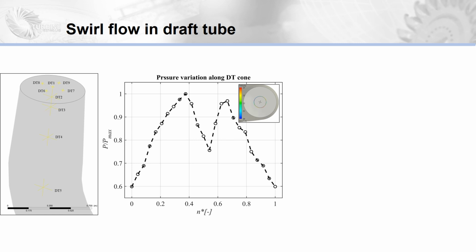The circular section was further divided into 25 equal points. Thus, up to mid-plane, the pressure gradually increases, reaches the maximum and drops by nearly about 25%. The pressure further increases and reaches nearly 97% of the maximum pressure and reduces to the same minimum value. This variation in pressure at the circular position of the inlet of the draft tube shows the swirl flow flowing from the outlet of the runner. The motion of swirl at this position is in a clockwise direction corresponding to the runner rotation.